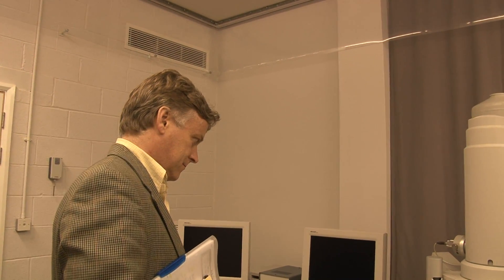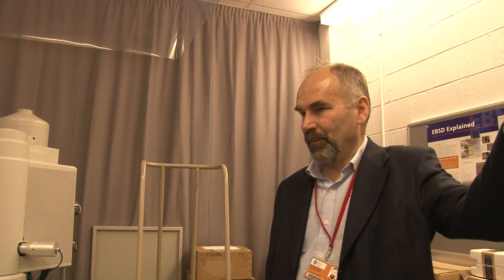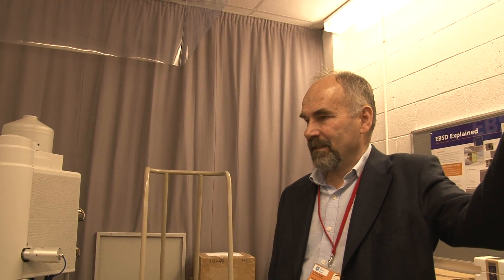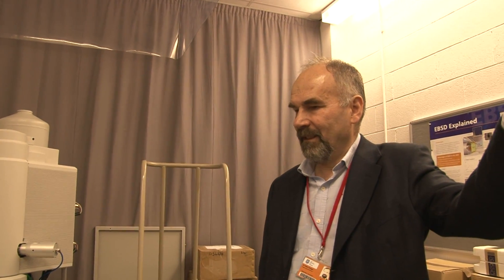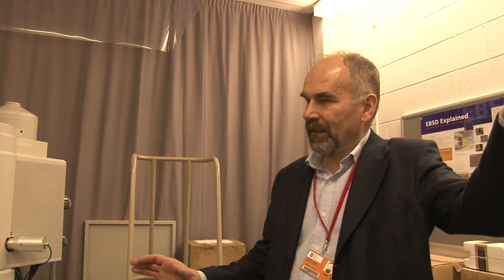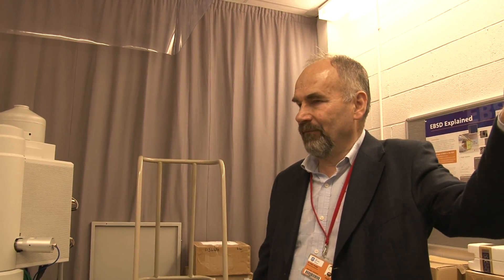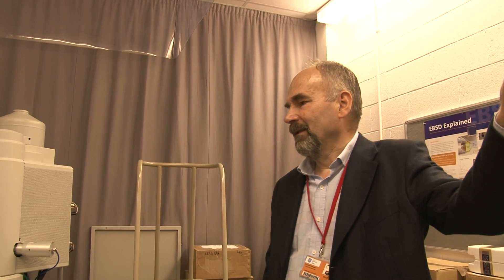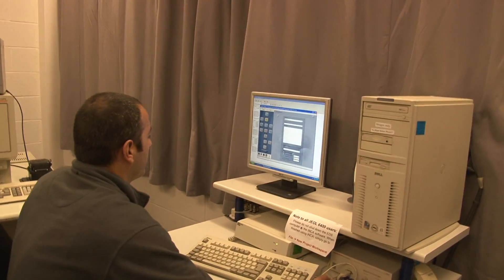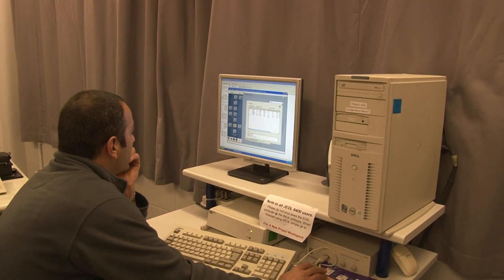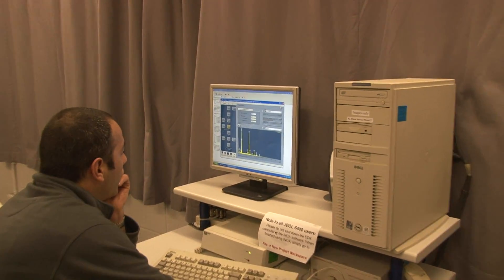This is a scanning electron microscope — field emission. Its resolution is on the level of one nanometer point to point. That doesn't mean that we can do analysis at the same level, because there is always scattering of electrons within the material itself, so they are spreading wider than the initial probe size. This gentleman is doing analysis of some materials — this is the spectrum, for example.